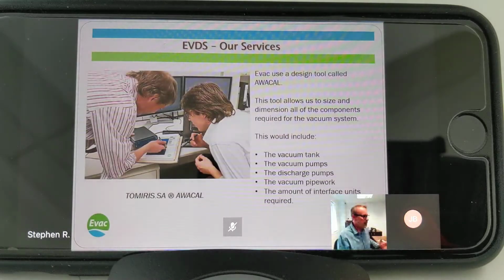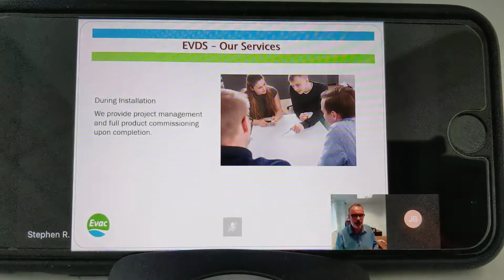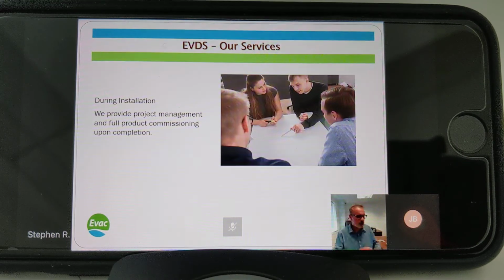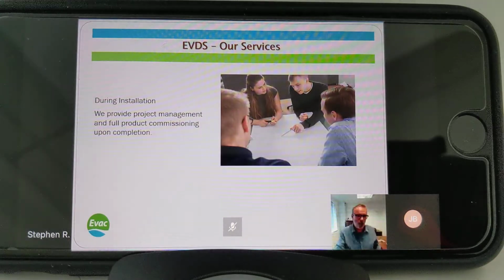During installation, we provide on-site project management, so it's not just dumped on the contractor. We have registered installers who put the system in, and we're on site during that time offering project management. At the end of a project, we go on to commission it - commissioning our equipment but also the installer's pipe work, making sure fittings haven't been put down wrong, branches pointing in the wrong direction, non-return valves the wrong way around. Everything's fully test commissioned, and at that point the warranty starts.